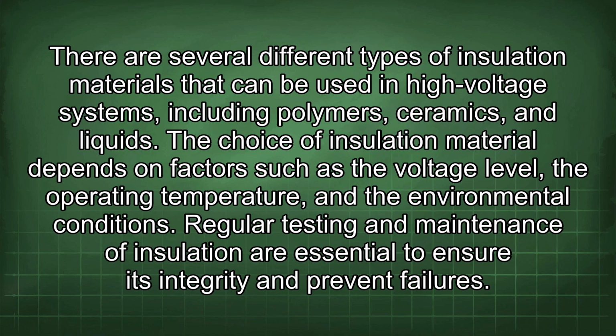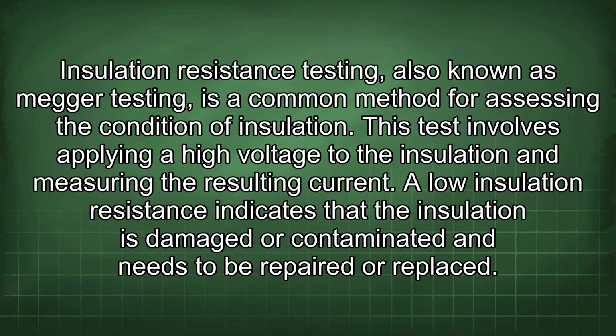Regular testing and maintenance of insulation are essential to ensure its integrity and prevent failures. Insulation resistance testing, also known as megger testing, is a common method for assessing the condition of insulation. This test involves applying a high voltage to the insulation and measuring the resulting current. A low insulation resistance indicates that the insulation is damaged or contaminated and needs to be repaired or replaced.